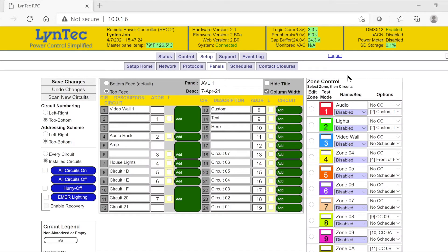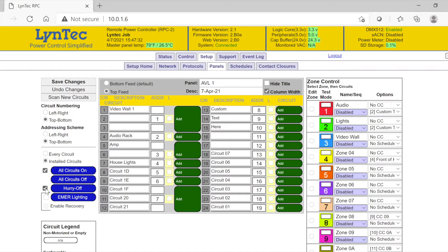Starting on the far left in the Global Command section, if you wish to enable the All Circuits On, Off, or Hurry Off functionality, check the appropriate box now. If your LCP panel is to be a part of any UL924 systems, make sure to check the box next to the Emergency Lighting button now.